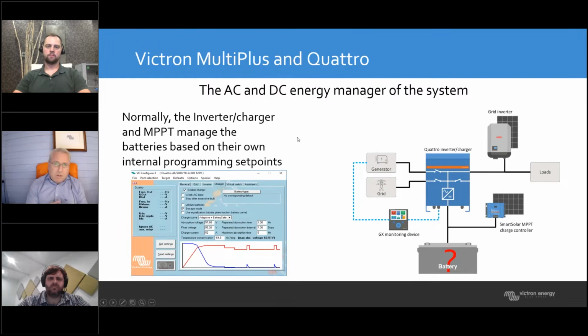So what you've all probably done under normal circumstances is consult with your battery manufacturer, say like Fortress, get the parameters for charging, and manually enter the charge parameters into the inverter charger so it treats the batteries the way the manufacturer wants. This gets the most out of the batteries and also provides safety, because particularly with lithium batteries, you have to be careful about overcharge and over discharge, to preserve your investment as well as ensure safety.